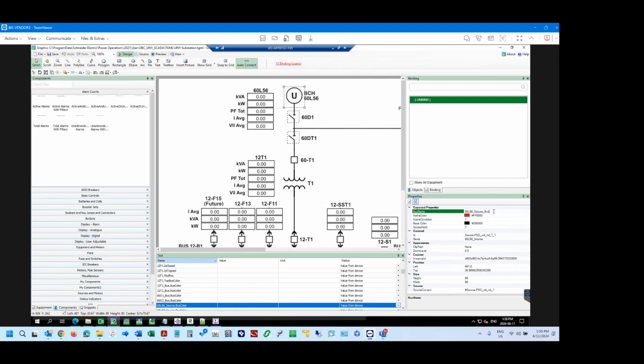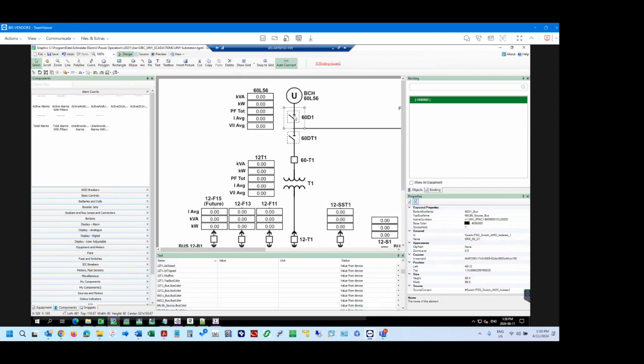So I typically go through, if I'm making a change, and I make sure that from the top, I copy that label, then I go to the next object down, literally click, naming this the same in the one line engine that connects those 2 points together. And then the same thing goes forward for the bottom bus name. This bottom bus name will only become active when the active condition closes the breaker or the switch, and then that active condition flows through that switch. And then that will in turn turn the bottom bus and the bottom bus name on.